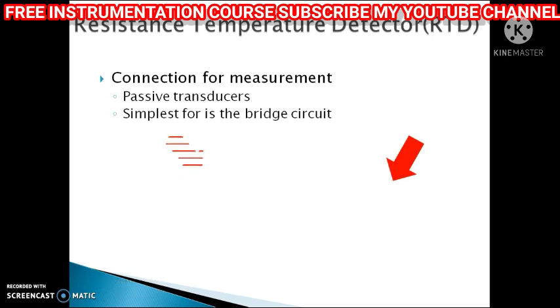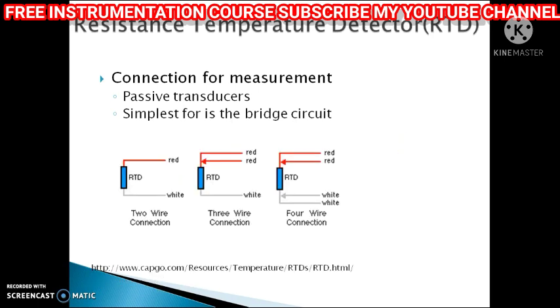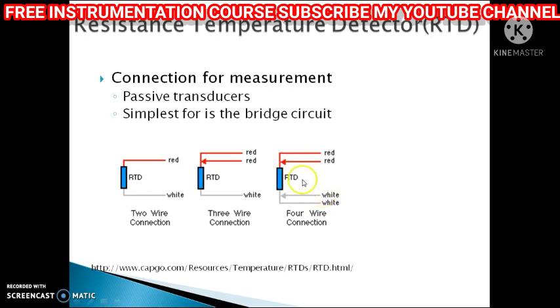RTDs are resistive devices, so lead resistance directly affects accuracy. The error can be quite large, and hence three types of connections are available. The two-wire connection has no compensation. In the three-wire connection, one wire goes to ground and two wires are used for measurement. For more accurate readings, the four-wire connection is used.